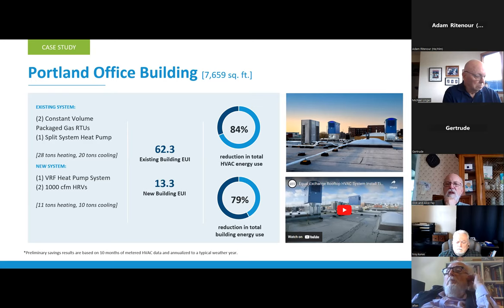And of course, we're energy efficiency engineers, so we were also driven to find an extremely efficient solution for this. So what we ended up doing was we replaced two constant air volume gas RTUs with a 10-ton VRF heat pump system. And we also installed two HRVs. The result from this retrofit was that we had an 84% reduction in total HVAC energy use and a 79% reduction in total building energy use, which is quite significant.